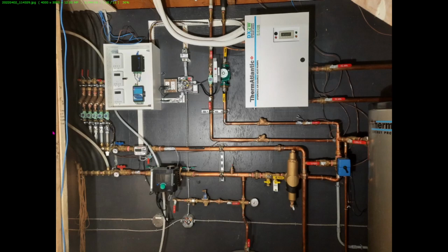In my final segment of the HVAC update video, I wanted to briefly go through the control hardware and software that is being utilized on this hydronic heating and cooling system. As previously mentioned, I'm using the DX2W EX1 air-to-water indoor module from ThermAtlantic. This is a coil heat exchanger that transfers the energy from a refrigerant set of lines to a water set of lines in this very compact 16 by 24 by 12 deep cabinet.